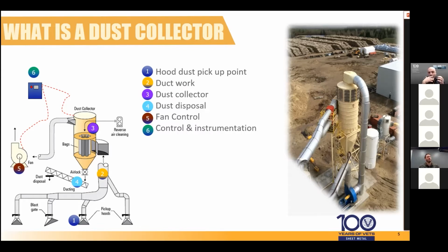At about one, if you look at the dust collection system. So you've got pipe that, let's say, is 12 inches. At 1 foot away from that opening, the velocity at that face will be about 10%. So if you have dust to capture and you're too far from the opening, there's just no really successful way to capture it.